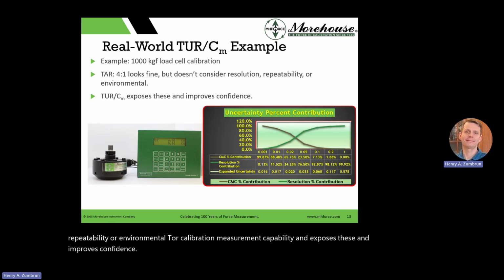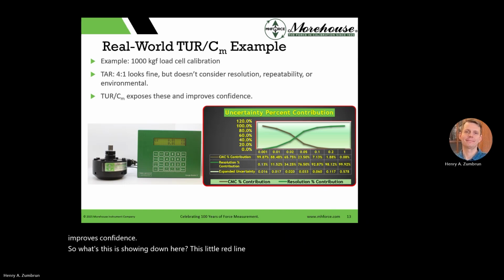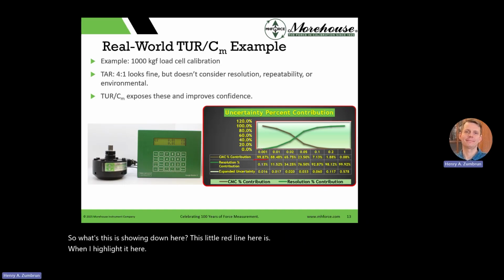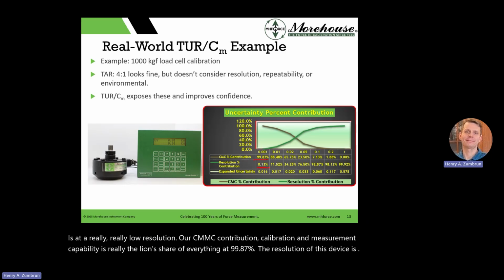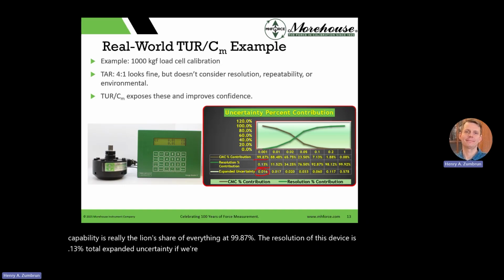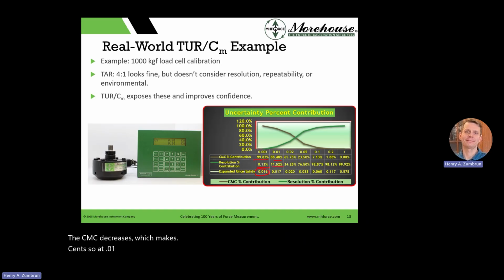So what this is showing down here, this little red line, when I highlight it here, is a really, really low resolution. Our CMC contribution, calibration and measurement capability, is really the lion's share of everything at 99.87%. The resolution of this device is 0.13%. Total expanded uncertainty, if we're looking at it in kilograms, equates to about 0.016. As that resolution increases, the CMC decreases, which makes sense. So at 0.01, resolution is now 11.52. Does the expanded uncertainty change too much?